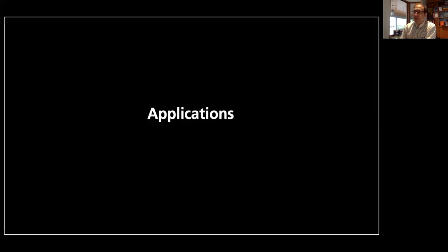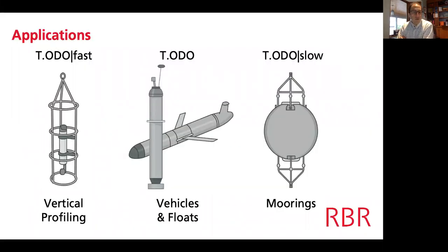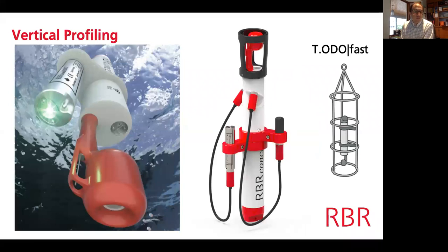Let's look a little bit at applications, how people are using these sensors in both fast, standard, and slow variants. As you can imagine, people are using the fast one mostly for vertical profiling, the standard for a variety of vehicles and floats, and the slow for a variety of moorings, both inline moorings and on-the-bottom moorings. So let's look a little bit more. Here you can see a very standard application for vertical profiling, connected to an RBR-CTD. Here we have the oxygen sensor and a turbidity sensor connected to an RBR-CTD for vertical profiling.